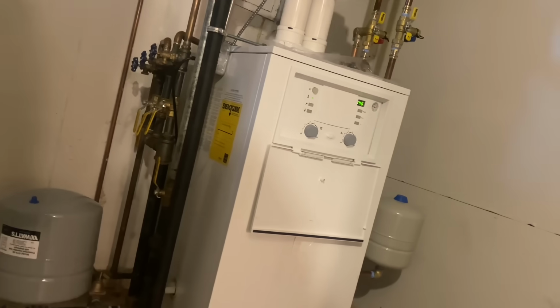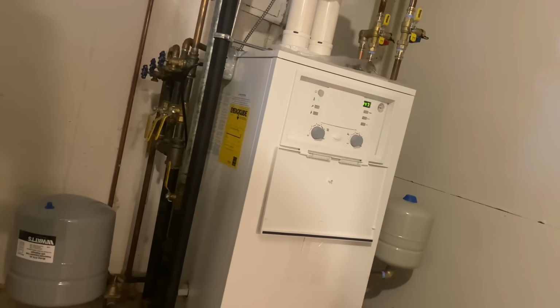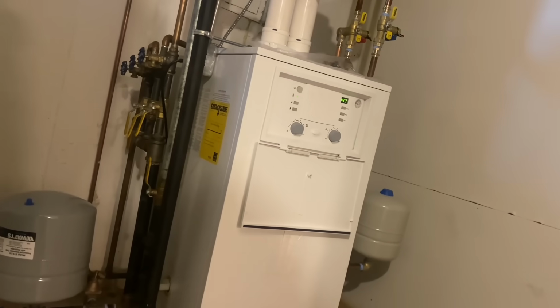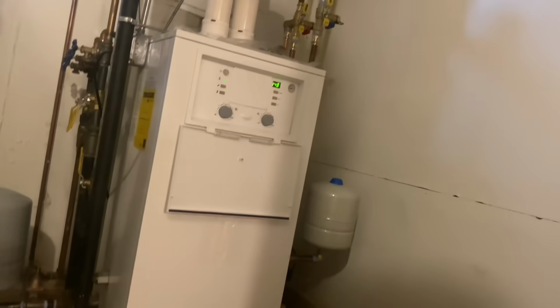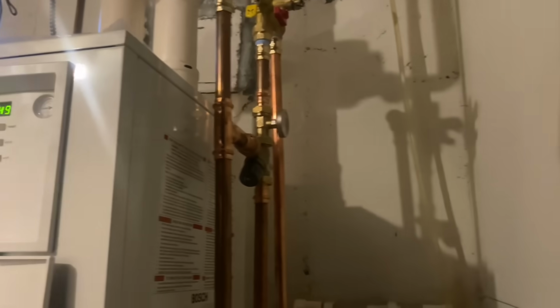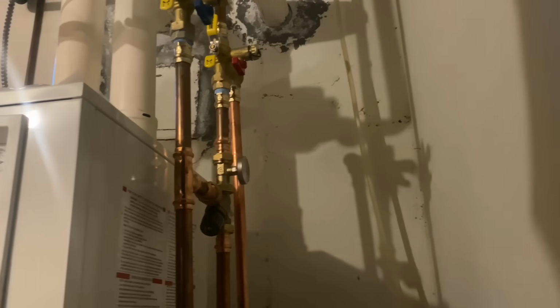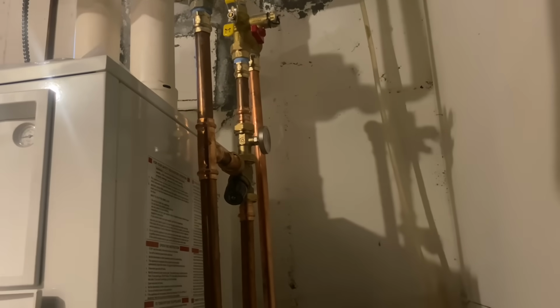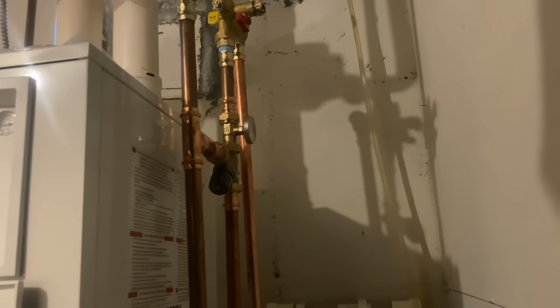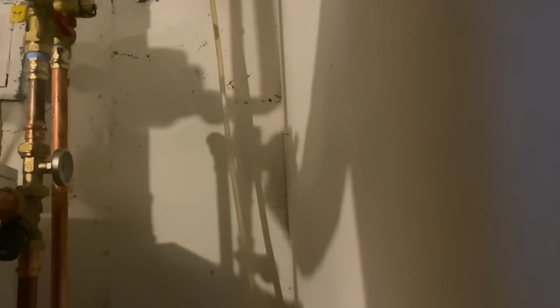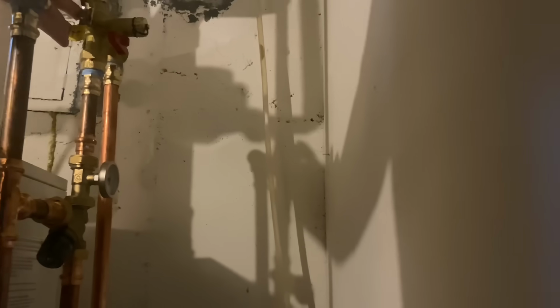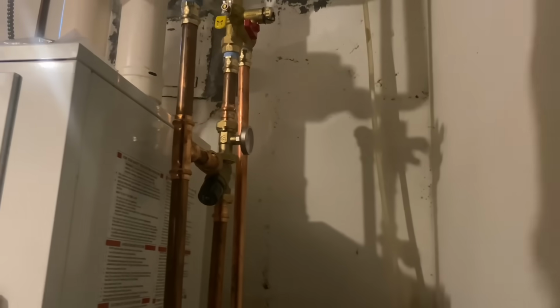And then we started not getting hot water to the showers. Both upstairs showers, maybe once every 10 times we get hot water. 9 out of 10 times it gets hot for maybe 20 seconds, goes away, and then it might get warm a little bit, goes away. That's all new. Yeah, this looks new. I don't think this was here before. It was not. So why was that added?